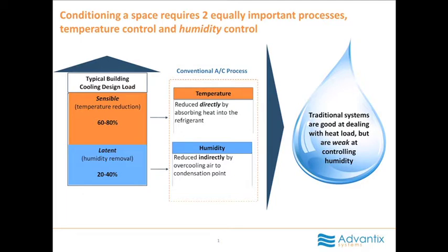And depending on how efficient that heat pump or heat removal system is, we saw a SEER or IEER 21.6 system that they talked about earlier. You can get rid of that sensible heat very efficiently. However, you talk about the humidity, and that same metal fin has no ability to directly extract moisture from the air. However, you still need to do that.